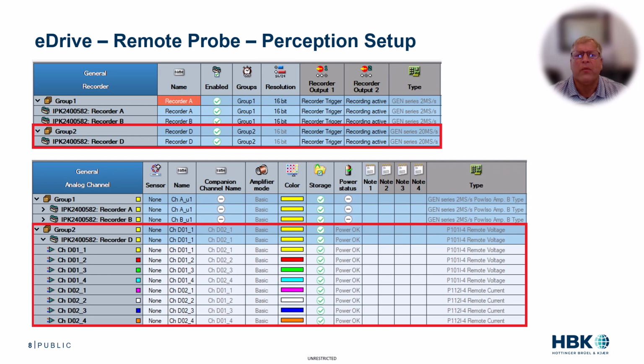Now, when I view a list of the analog channels within the settings sheet, I can see a list of my voltage and current remote probe channels on recorder D, and all 8 have a power OK power status. The first set of 4 channels on recorder D are voltage, and the last set of 4 channels on recorder D are current.